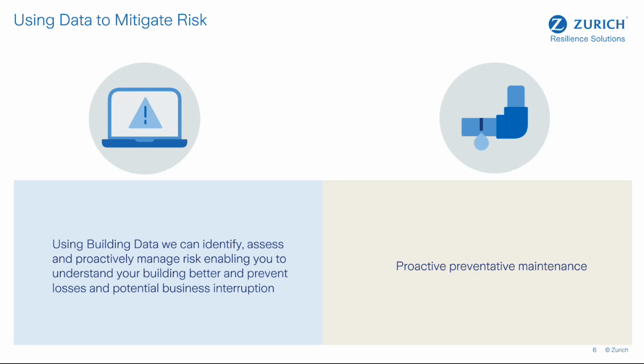There's quite a number of areas, but I'll go through the top 5 areas that I think are important. Fire suppression, including sprinklers. There's a lot of information that comes out of building data in relation to this when you have that sort of system in place. It covers things like pressure loss, the water pressure itself, valves open, water supply levels, pumps working excessively. These are all massive bits of information we can use to make a judgment as to whether or not our suppression system or sprinkler system is working effectively.